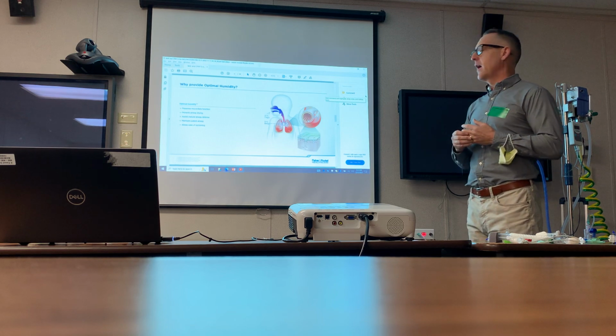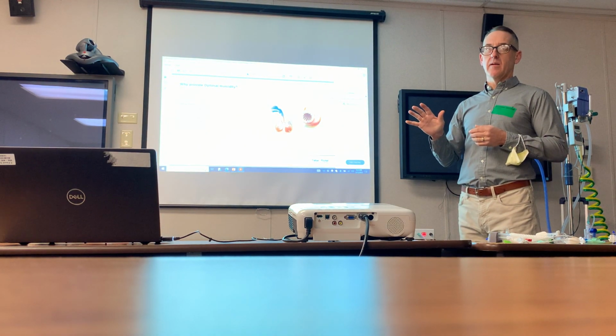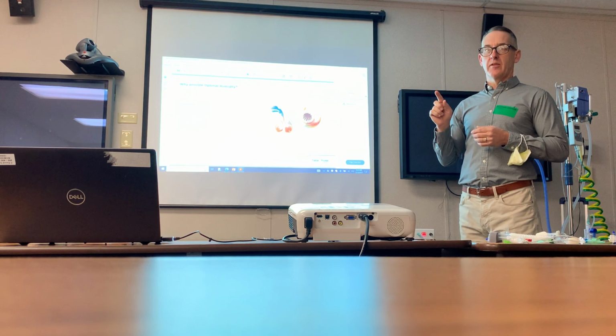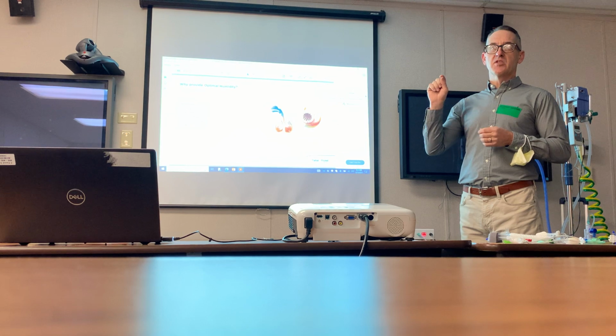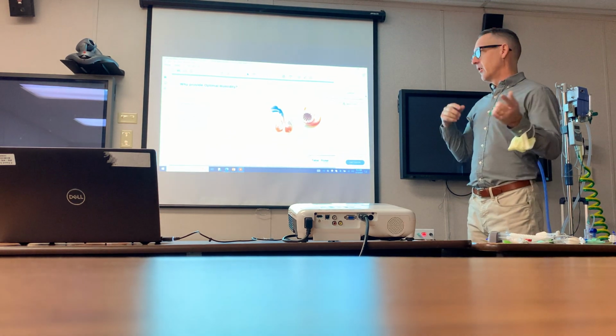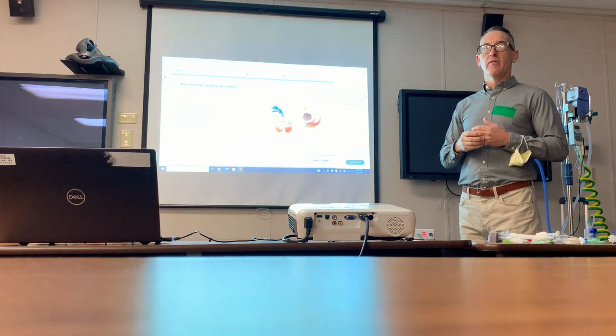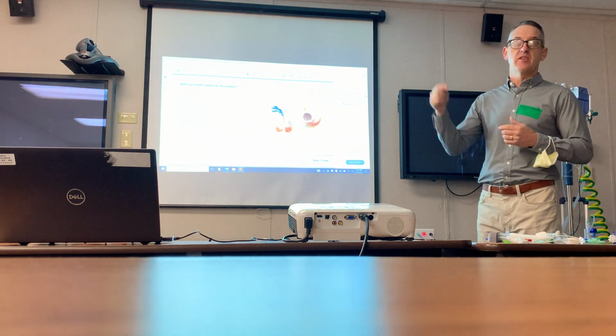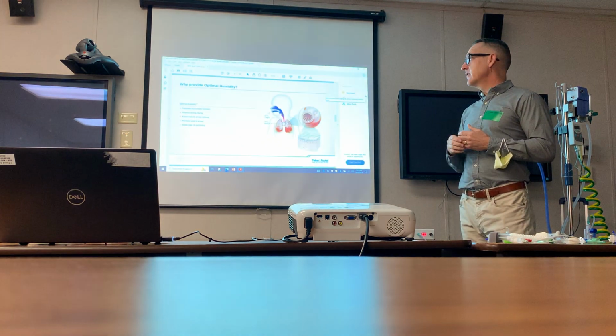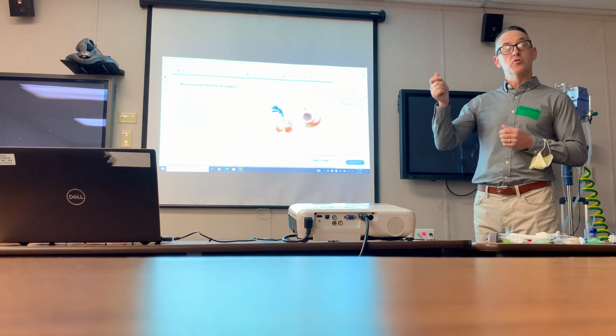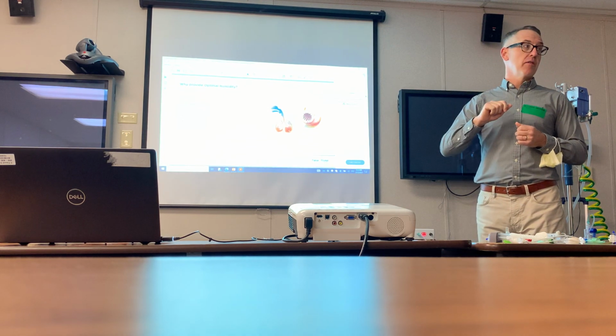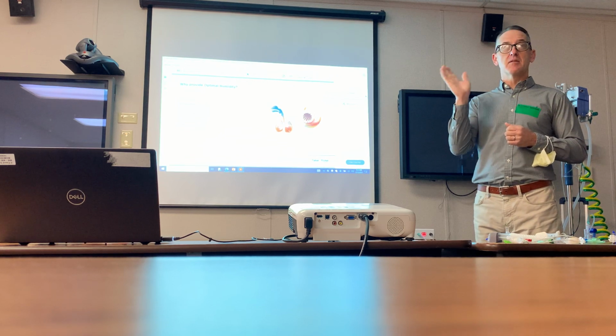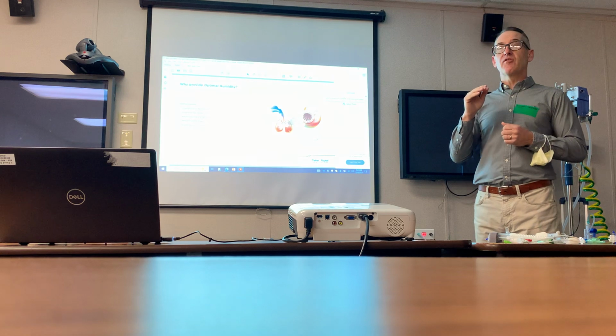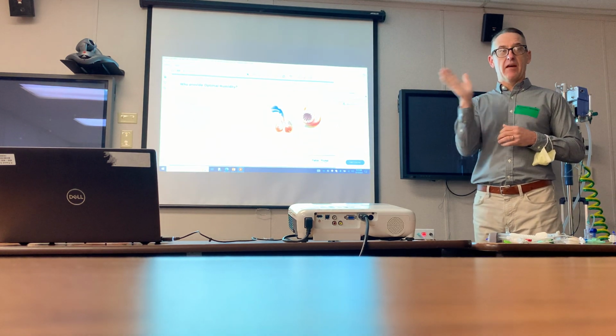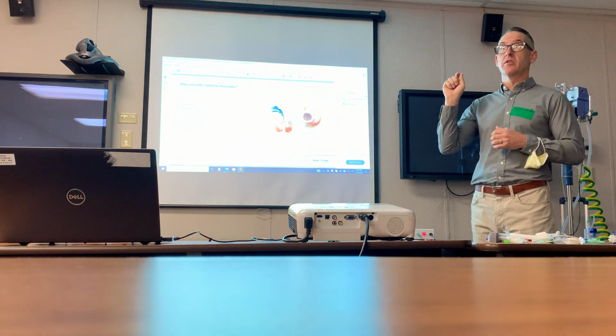Real quick on humidity, there's a lot of discussion on humidity, why we provide optimal humidity. Optimal humidity can only be achieved at 37 degrees Celsius on the heater. That is what's considered 100% optimal humidity. It's a completely different talk what happens when you decrease that temperature from 37 down to 34 or 31. But it does have an impact on mucociliary function when you decrease the temperature simply from 37 down to 34 degrees. After about 15 minutes, the mucociliary function starts to slow down, and after about an hour, the entire area starts to dry up and pathogens are no longer being moved along, just by that simple decrease of temperature.